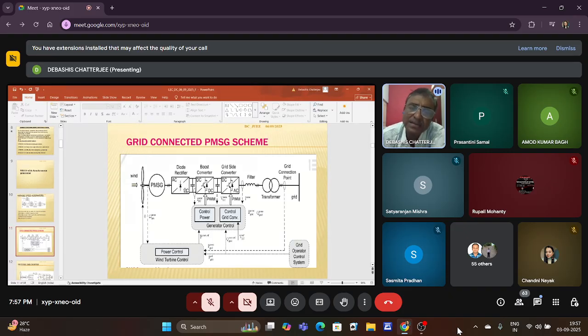So normally, another converter is required, known as an active front-end converter, which can be used to demagnetize the field at higher speeds. It is a bidirectional type of converter. It will provide some excitation in the opposite direction when the wind speed increases above certain levels, and then the field excitation can be made constant. But again, there is a large converter, large cost, etc. All those things come in. So this permanent magnet synchronous generator also is a good scheme under variable frequency, or rather variable wind speed situations. But normally this is restricted for cost purposes, or you can say space.